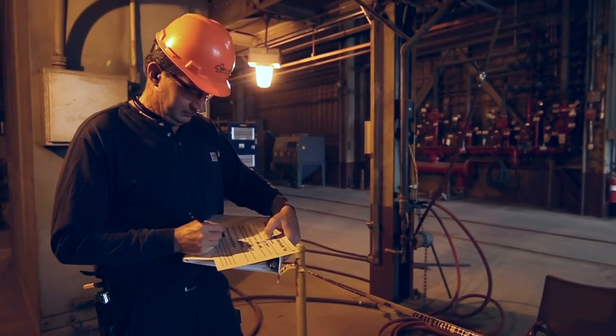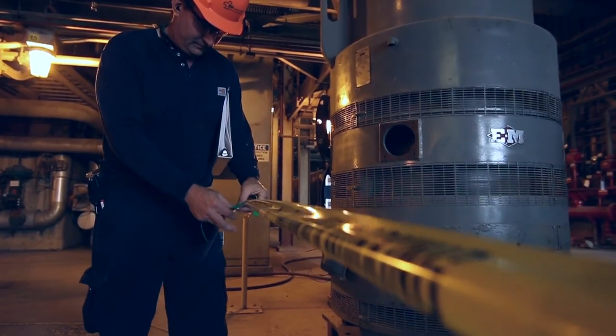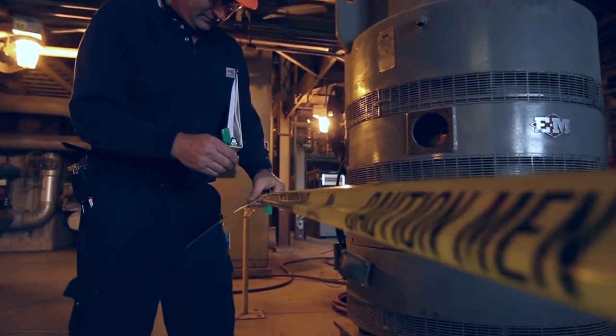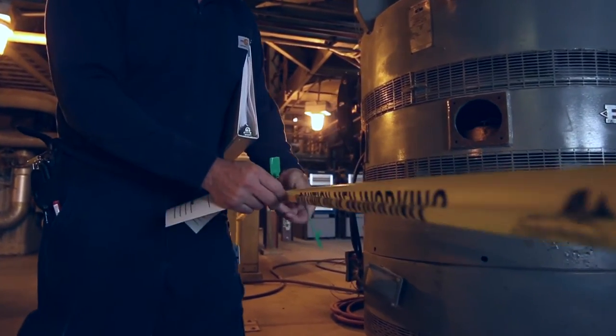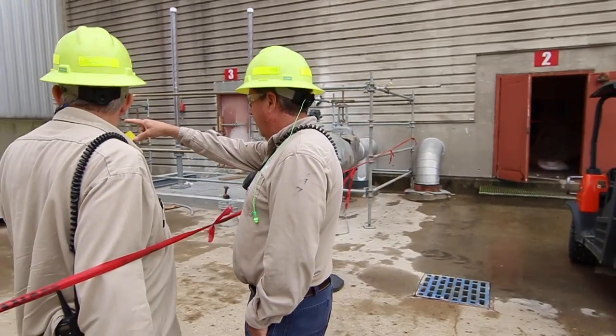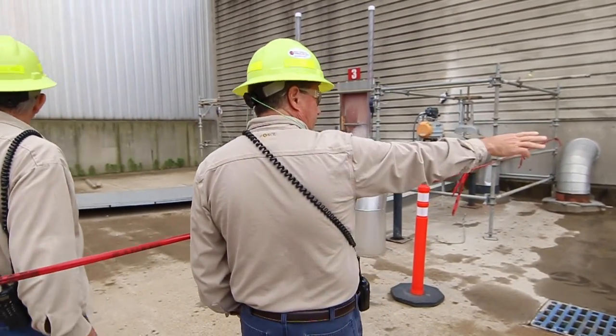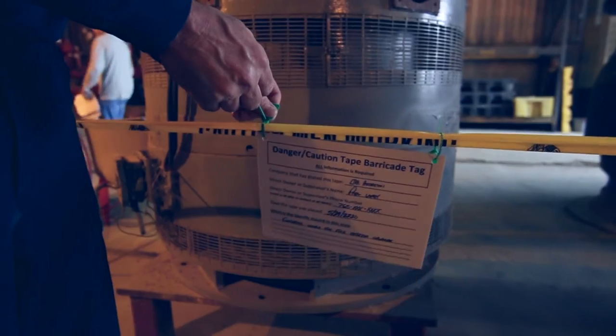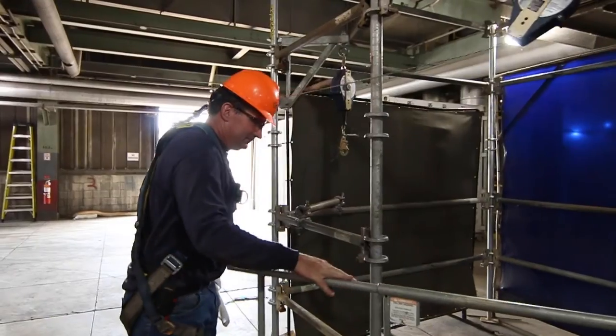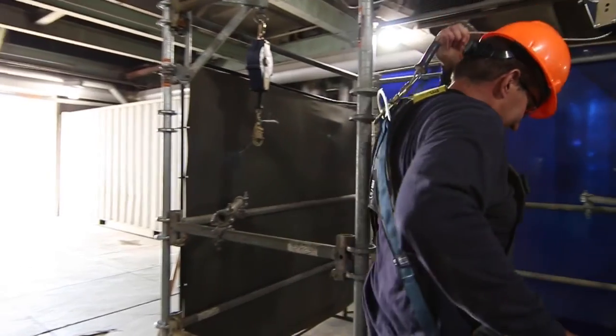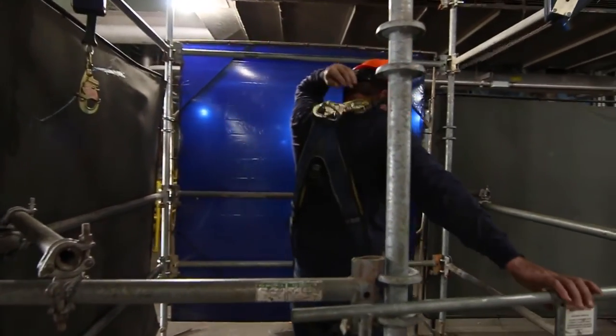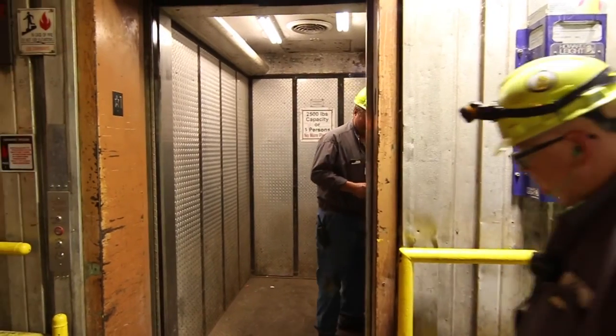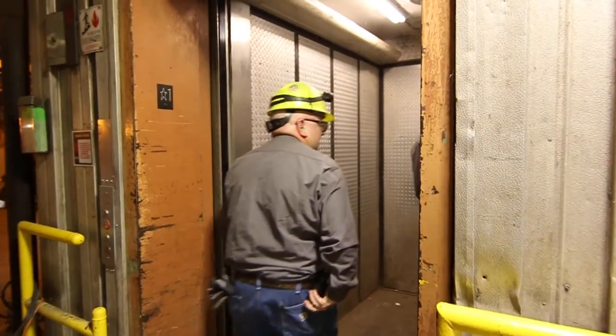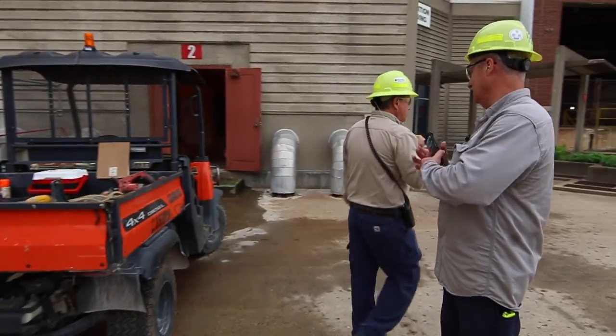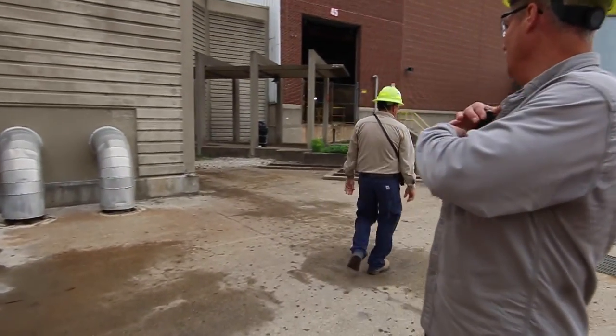Caution or danger tape shall include an informational tag that lists the name of the person who hung the tape and the date, time, and purpose for the barrier. Whoever is controlling the area with red or yellow tape shall put their direct contact phone number on the tag. If a hazard is created that requires a hard barricade, all barricades shall meet OSHA requirements. For your protection, you are required to stay in your assigned location unless you receive authorization from the contractor administrator to enter another area of the facility.